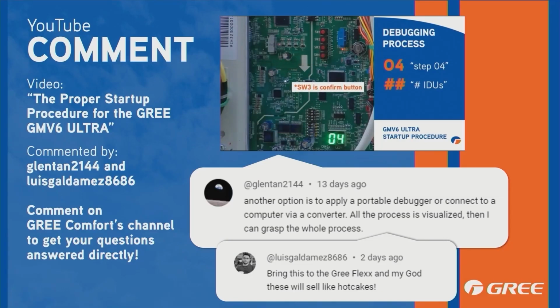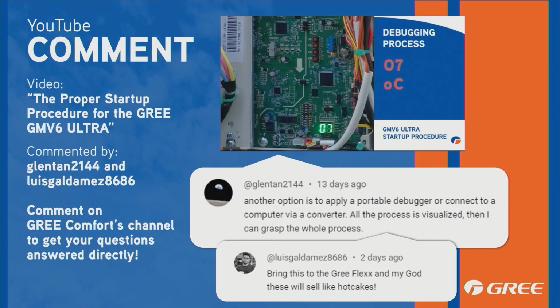You can also look right on the service panel of the door. It gives you all the error codes. You could have a very simple error code. I'll give you a simple example of one that I dealt with, where the guy was going through debug, and all of a sudden, I forget the error code number right off the top of my head, but it was stuck right there. And I look up the error code. I'm like, okay, you've got no power to the indoor unit.